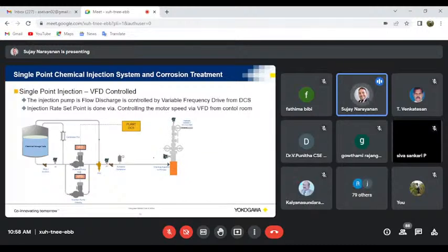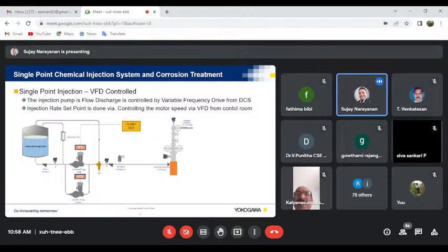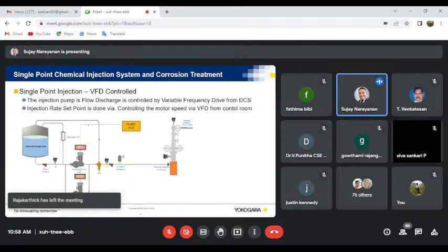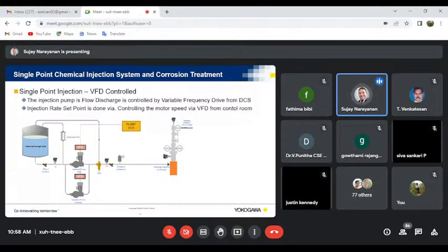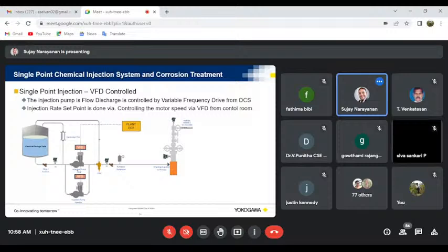Now in this type, for the injection rates, the operator needs to go to the field and adjust the stroke on the pump. Now you have some pumps equipped with a variable frequency drive or stroke controller. So you can send a signal from the plant DCS to control the VFD, and the VFD in turn controls the stroke length. This will be a 4 to 20 milliamp analog signal, where you can adjust the pump stroke length. So this is a remote control.